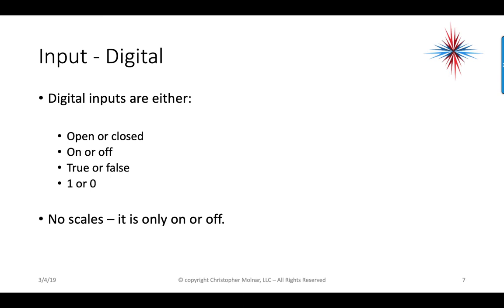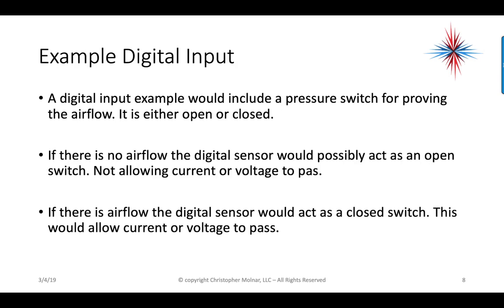The digital input is a little bit different. It's either open or closed, on or off, true or false, or in machine language, 1 or 0. It can only have two values. An example of a digital input would be a pressure switch for proving airflow — it is either open or closed. We either have airflow or we don't. If there's no airflow, the digital sensor would act as an open switch, not allowing current or voltage to pass. If there is airflow, the digital sensor would act as a closed switch, allowing current or voltage to pass.